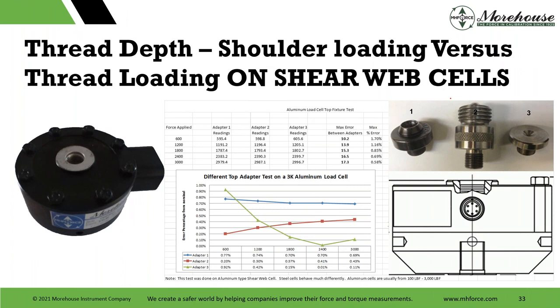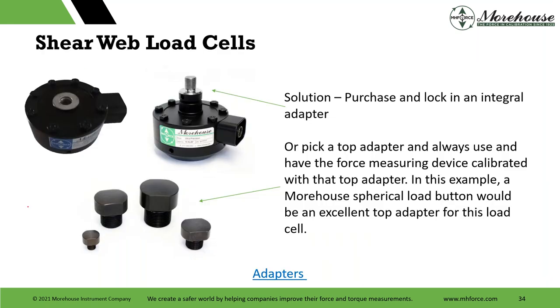For sure. I said something about thread depth and loading. Here's a 3,000 pound load cell, and just varying these top adapters on the cell produced a max error of 1.7%. So very, very high error from just switching out adapters. The right thing to do is install an integral adapter, which is in this picture. I recommend everybody buy load cells with this installed.